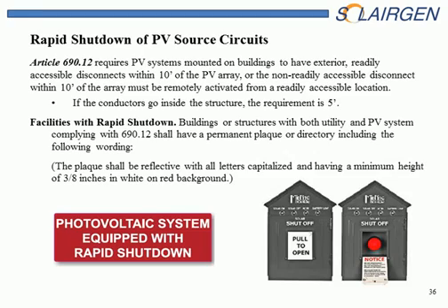And there should be a label that states, PV system, rapid shutdown system in place. So you may not see this. This is a new requirement, so you may not run into this for a little while, but you should start seeing this on all new systems if you happen to be out on one of them.